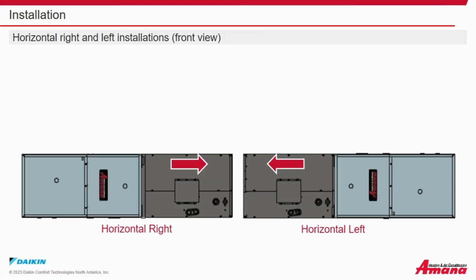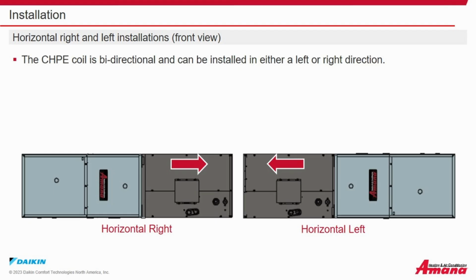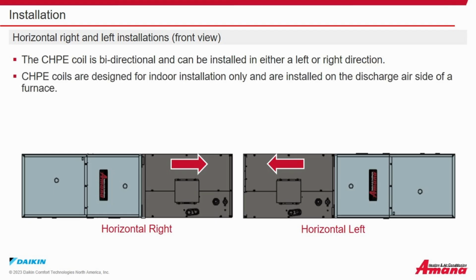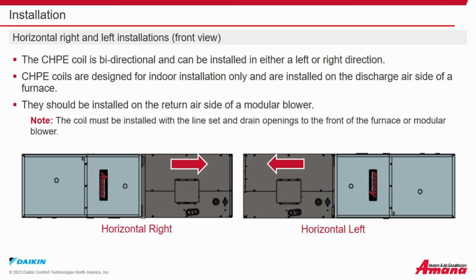Horizontal right and horizontal left installations, front view. The CHPE coil is bidirectional and can be installed in either a left or right direction. CHPE coils are designed for indoor installation only and are installed on the discharge air side of a furnace. They should be installed on the return air side of a modular blower. The coil must be installed with the line set and drain openings to the front of the furnace or modular blower.